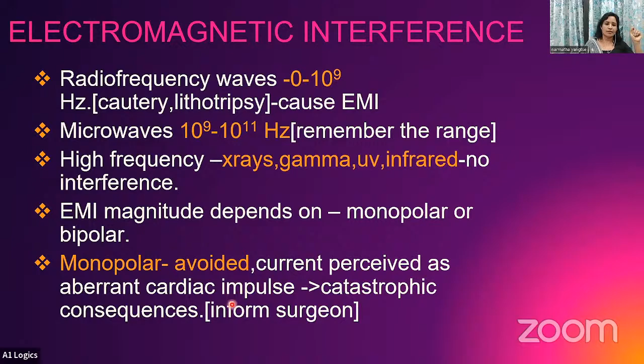Here you can see in the monopolar, the current is passing through the body from the anode to the cathode. So it will be detected by the pulse generator as the patient's own heart rate, or it can be considered as arrhythmias. Whereas in a bipolar, the current passes only between the two ends. So that is why monopolar is very dangerous.